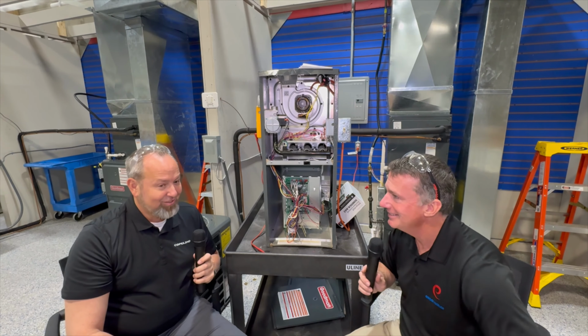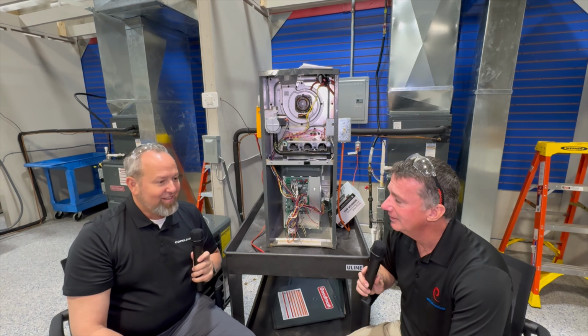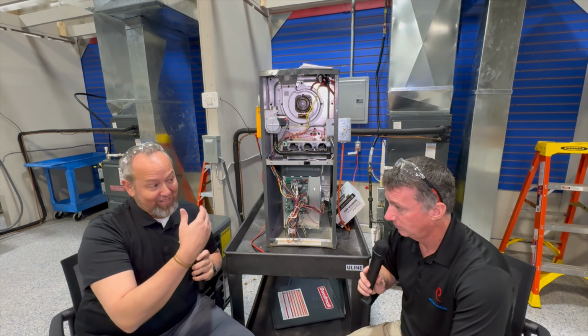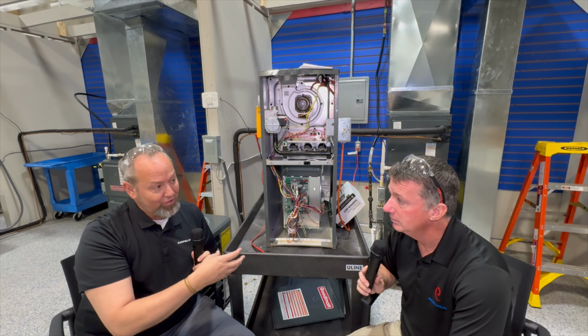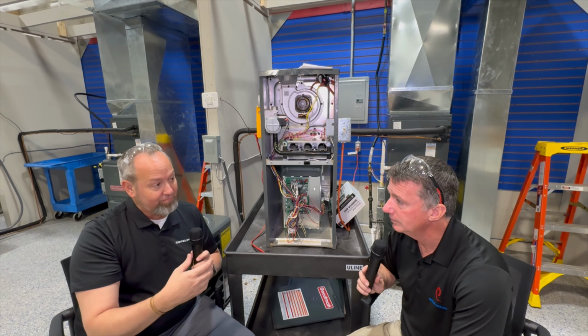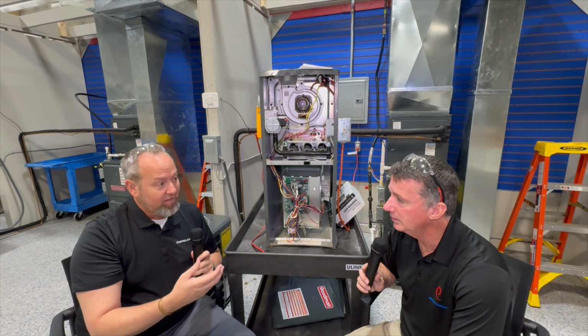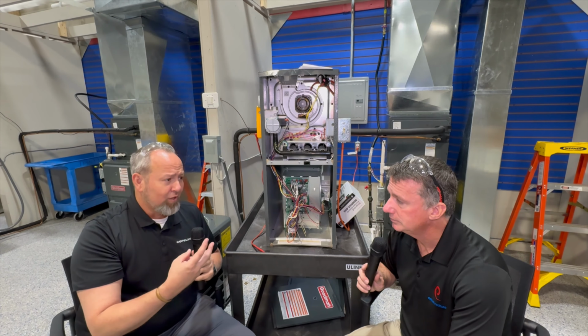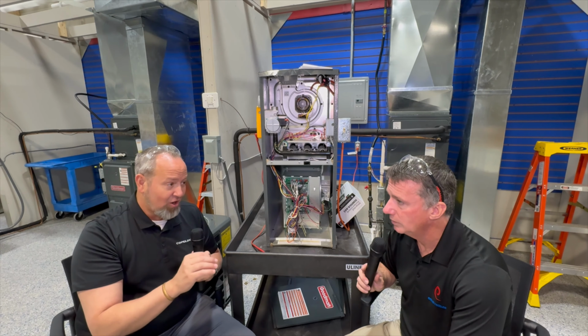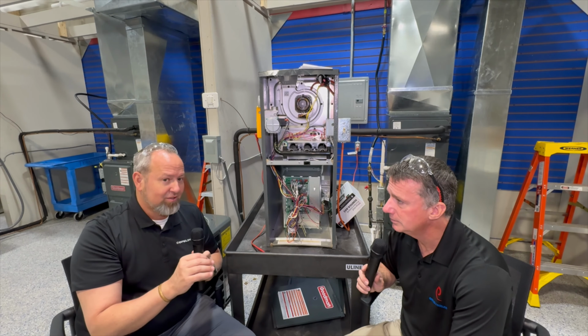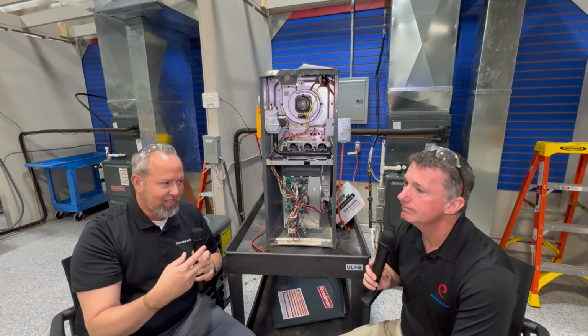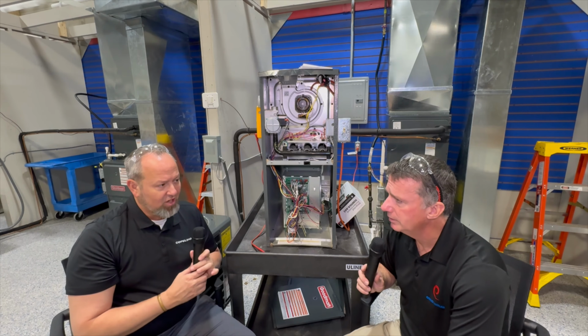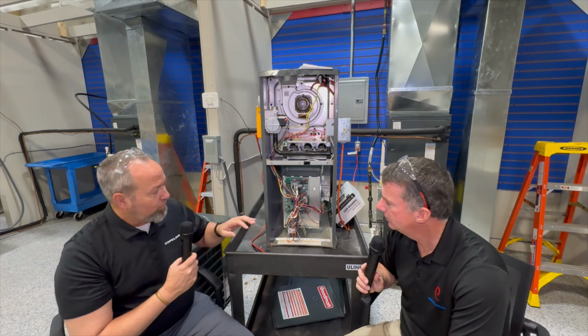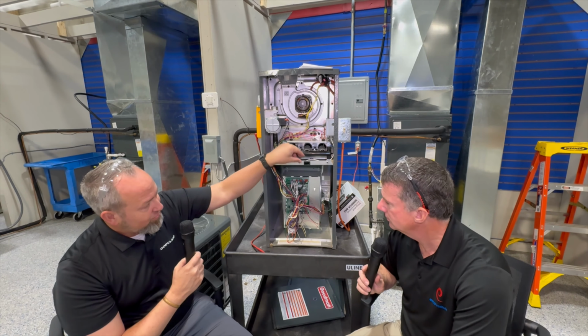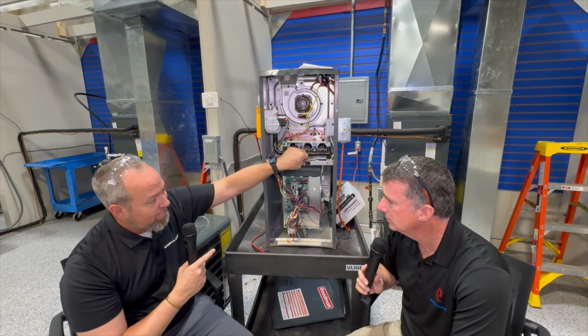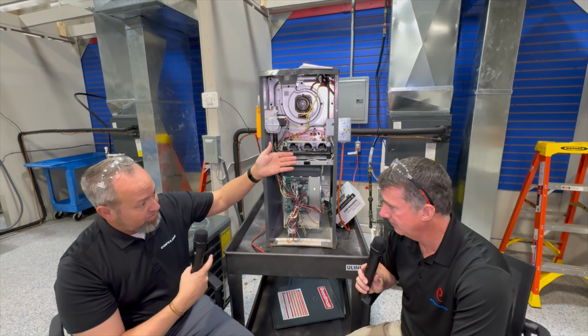Absolutely, so the idea is, if everything is functioning properly and you power it up, it will tell you, okay, this is the harness configuration. And it requires that twice to lock in that harness to make sure. So how do you get that second harness configuration lock-in while you're there? Well, typically when you're testing the board the first time, you have the door switch closed, and that's the first time you're going through. It recognizes the 24 volts AC.